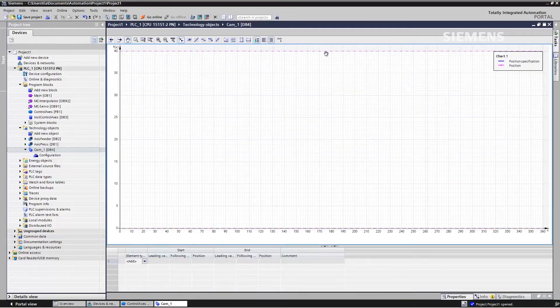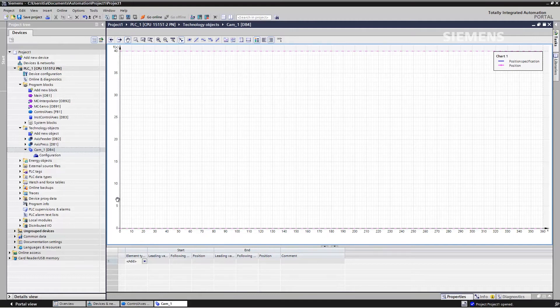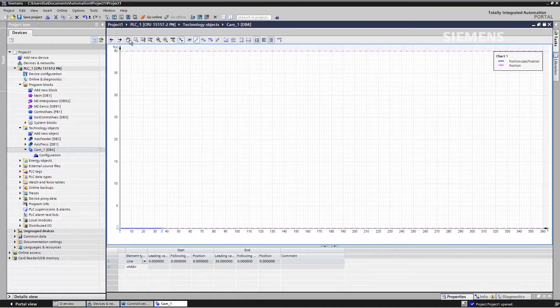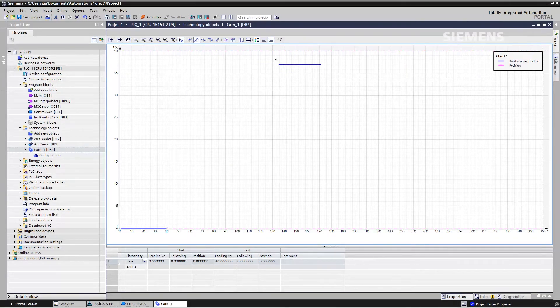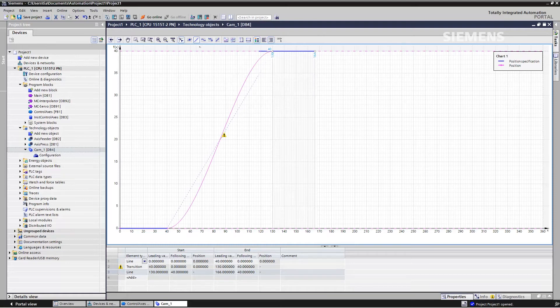We can specify the CAM disk either graphically or using the table at the bottom. We'll choose to do it graphically, defining the position of the slave axis for each position of the master axis, the press. If the press moves between 0 and 40 degrees, the infeed continues to stay at 0. If the press moves farther, the infeed should then move forward, and if the press has arrived at 130 degrees, the infeed should stop at its right-hand position during the press cycle.